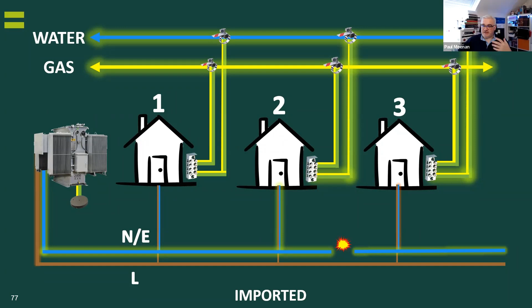Then over time, that cable, which could be a 70-year-old plus PILC lead cable, some could be doing groundworks, or it could just be wear and tear. It could go faulty, it could go bang, it could be an old joint that just breaks down, goes high resistance, and eventually you break the neutral. And then what happens is the current that's trying to get from number 3 back to the substation will divert on the water or gas main into 2, some into 1, and work its way back. And that's a phenomenon known as imported or diverted neutral current.